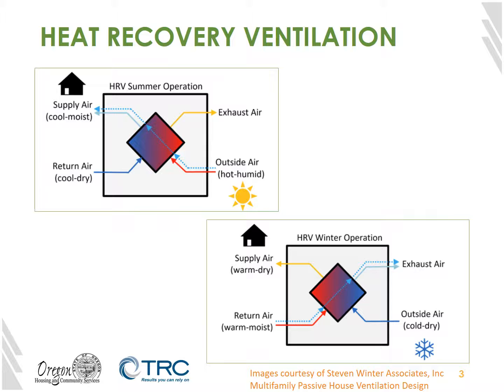In the Northwest, particularly in spring, an HRV can also add additional moisture to the building through the ventilation cycle because the heat is transferred from the incoming outside airstream to the return airstream leaving the building, which cools that supply air. But the exterior moisture is not removed from the incoming air. This building's dehumidification load then increases as a consequence of additional moisture from the outdoor air. Again, this is potentially really only a con in the spring in the Pacific Northwest. It is a much bigger concern in other parts of the country.